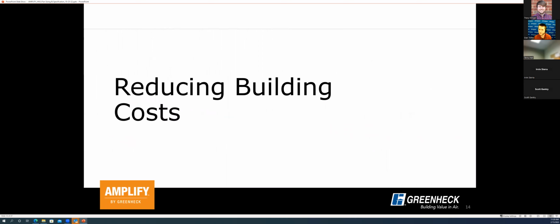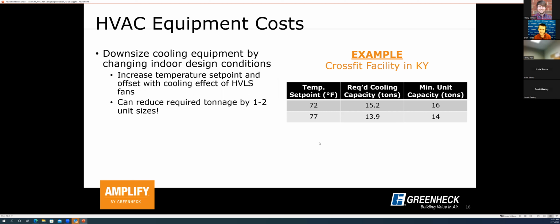The other couple applications that I mentioned earlier that we'll spend some time on are a little bit lesser reason for using an HVLS fan, but we're starting to see more and more momentum here. And really probably the most important one outside of that thermal comfort application is reducing building costs. So I mentioned this earlier, but HVLS fans can be used to help offset the first cost of an HVAC system by either downsizing or reducing the need for other types of equipment in the project. So here's one example of how this can be done. HVLS fans can be used very effectively to downsize cooling equipment in a conditioned space by essentially just changing your indoor design conditions and using the HVLS fan to offset that temperature change.